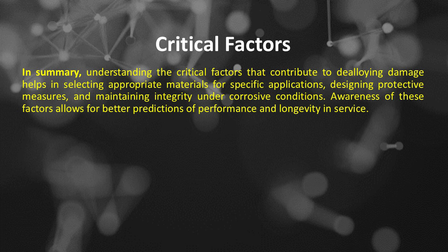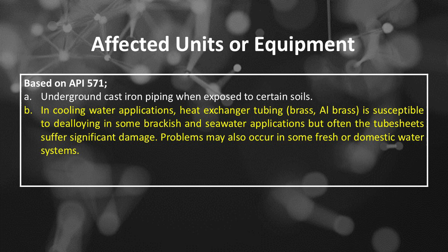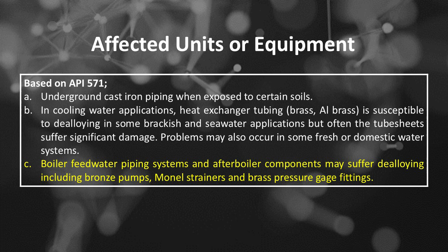Dealloying damage affected units or equipment based on API 571. Number A, underground cast iron piping when exposed to certain soils. Number B, in cooling water applications, heat exchanger tubing, brass, is susceptible to dealloying in some brackish and seawater applications, but often the tube sheets suffer significant damage. Problems may also occur in some fresh or domestic water systems. Number C, boiler feedwater piping systems and after-boiler components may suffer dealloying, including bronze pumps, Monel strainers and brass pressure gauge fittings.